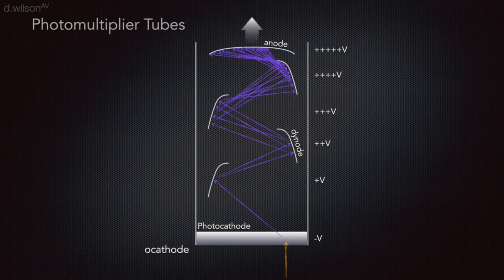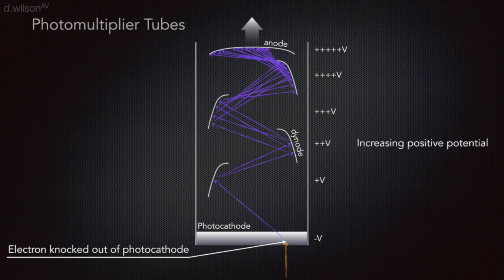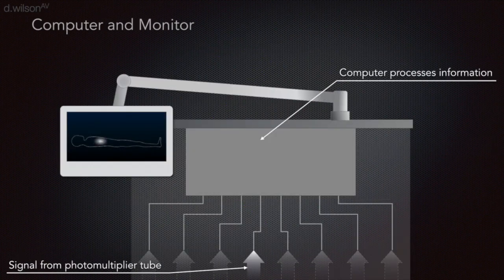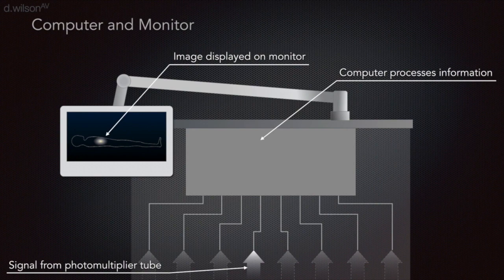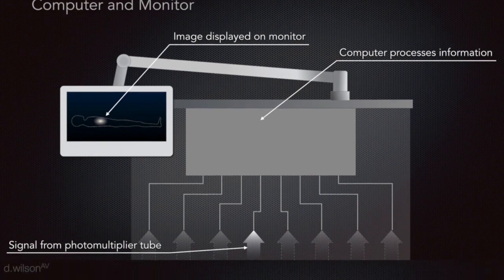The signals from the photomultiplier tubes go through an analog-to-digital converter and then to a pulse-height analyzer. This device detects the intensity of the signal, and thus the energy of the incident-absorbed photons, and uses only photons from the radionuclide when forming the final image.